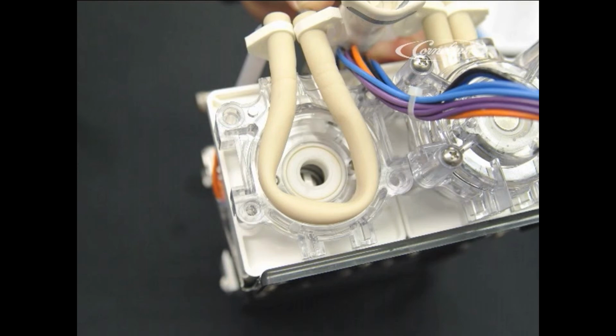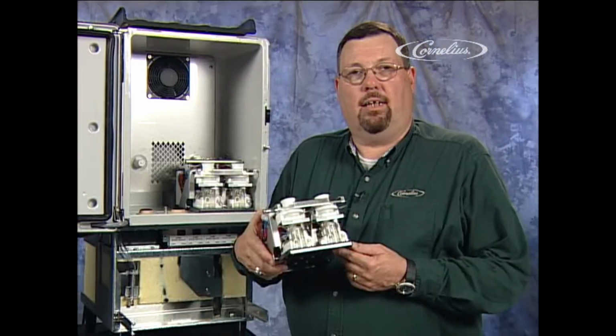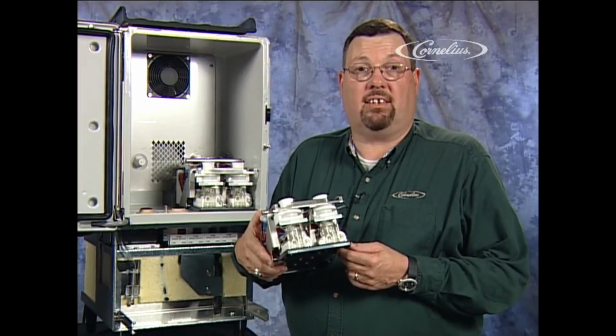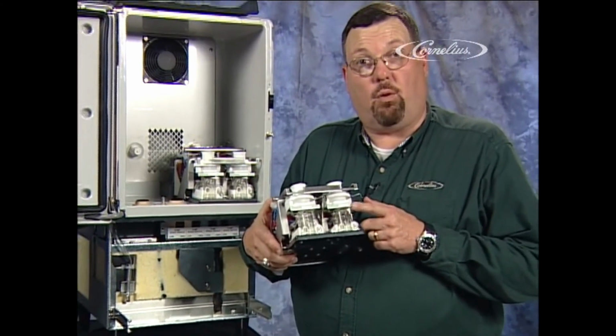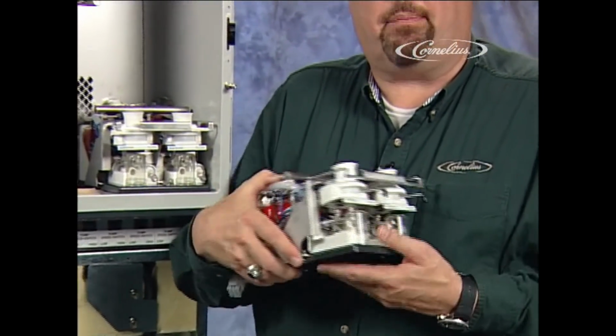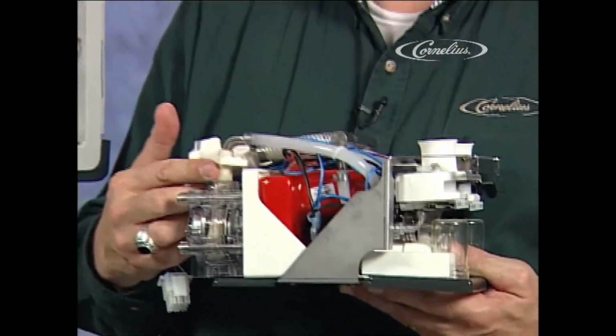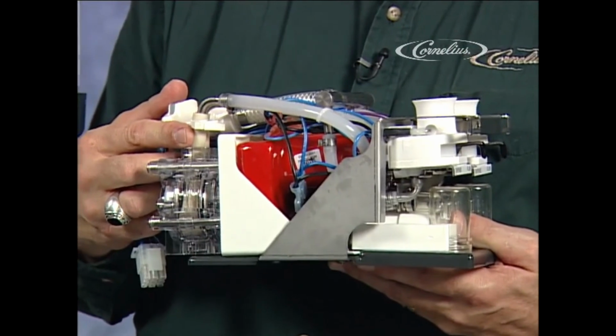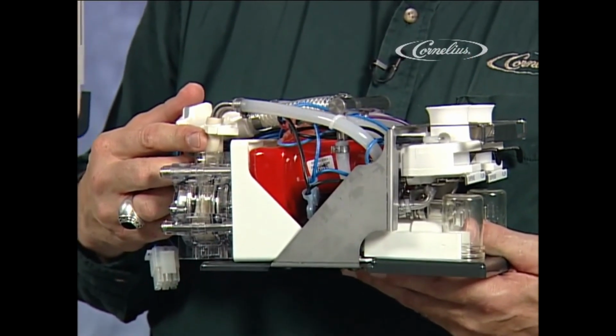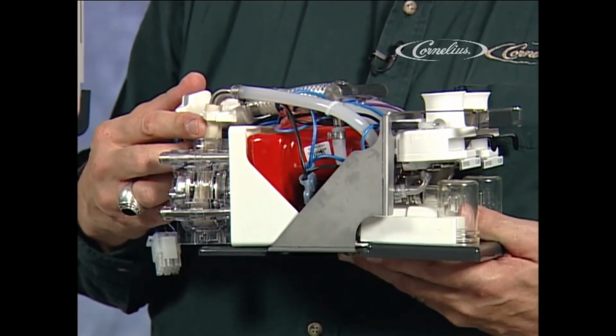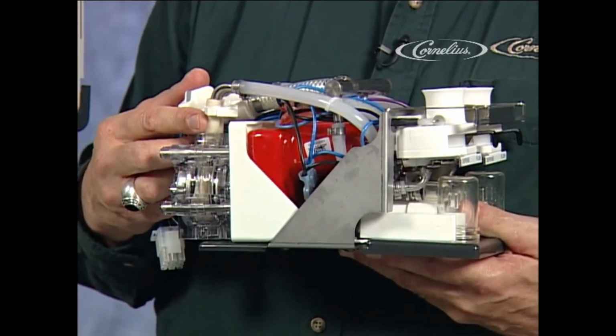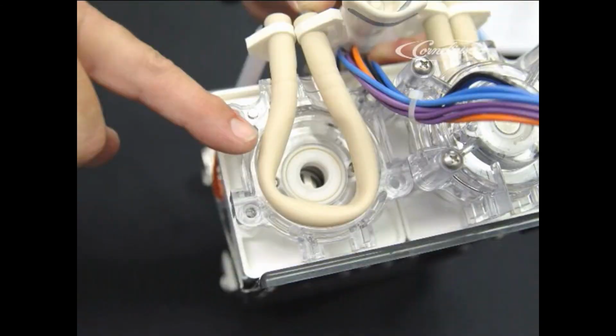We recommend a once-a-year change-out or any time a unit has been sitting idle for long periods of time. A key point to remember is if the customer consistently uses the flush mode to dispense water only, the pump tube at the top of the pump inlet eventually is going to balloon and then split. Flush is for flushing only, not dispensing water. This condition is more likely to happen when the incoming water pressure to the unit is over the recommended 50 psi. When reassembling the pump assembly, be sure that the tube is placed in the pump head grooves and is not pinched where the front and back halves are reassembled.